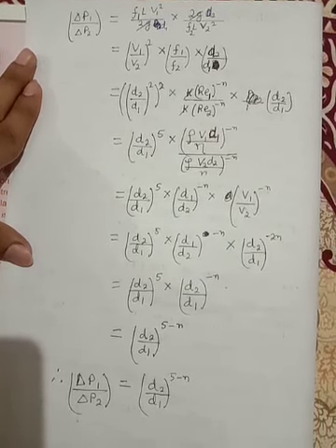Velocity of fluid in both the pipes is given by the ratio (d2/d1)², and since the friction factor is dependent on the Reynolds number, which is further dependent on the velocity and diameter of the pipe flowing the fluid, this also affects the pressure drop across the pipes. Now from calculation we can see that the pressure drop ratio across both the pipes is given by (d2/d1)^(5-n).